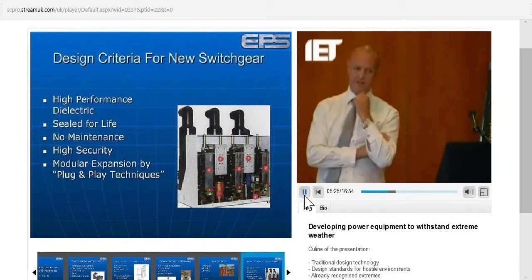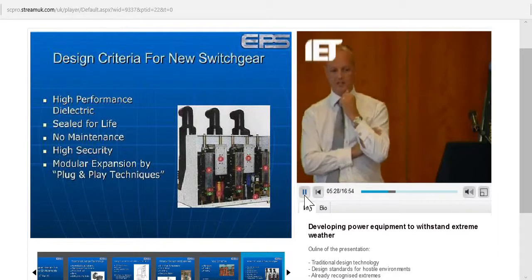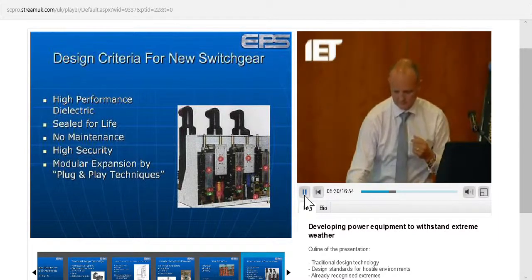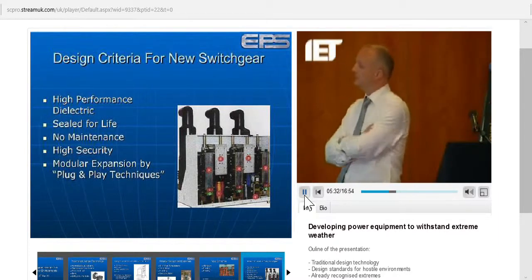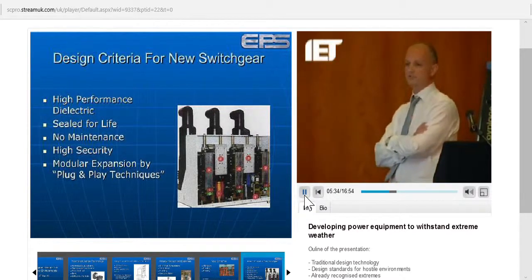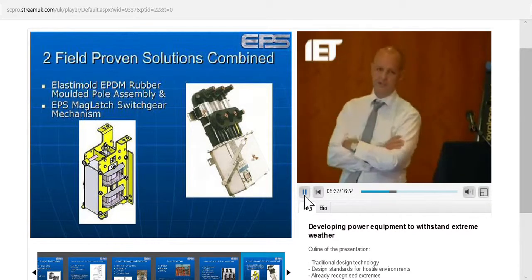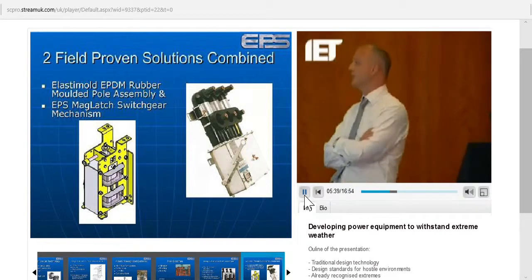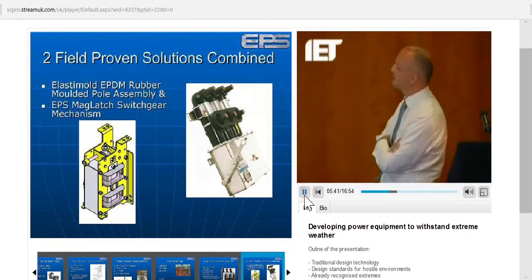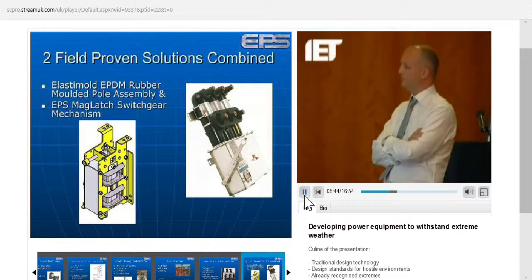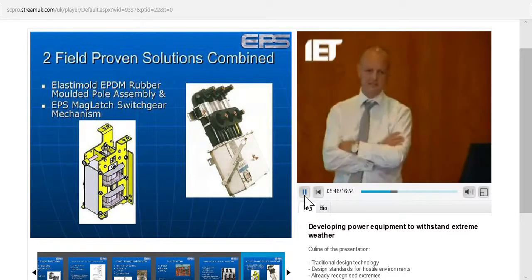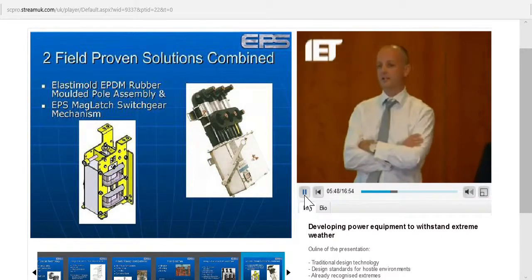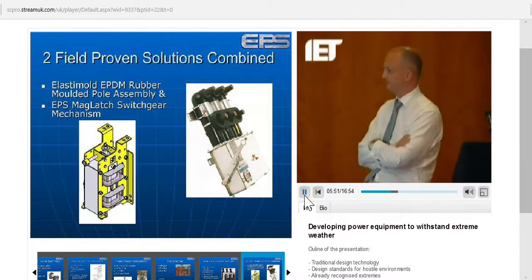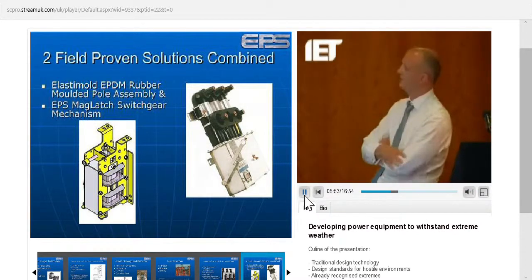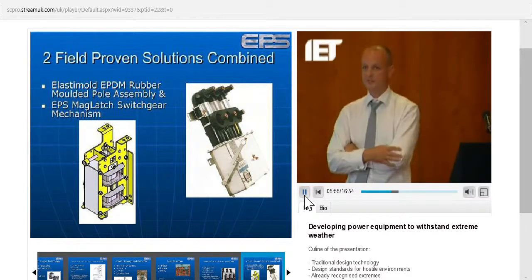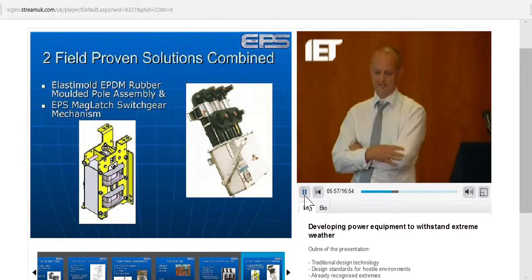The second item I passed around was a modular circuit breaker, at quarter scale. Together with Elastimold, we've used their technology—EPDM rubber insulation systems over-molded by a conducting layer—to create a circuit breaker pole, and added the EPS magnetic actuator mechanism to create a maintenance-free circuit breaker. Both technologies are field proven, but this is the first time they've ever been brought together.